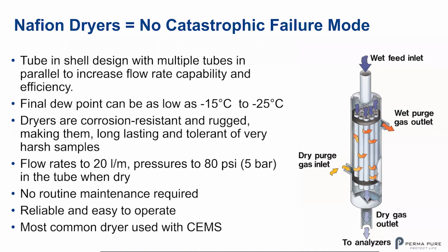So let's take a look at our PD series here. That's the type of dryer that we build into our systems. Those are shown there on the right. It's similar to the other one, but the difference is we have multiple tubes in parallel. The thing I want to talk about with these is that we have no catastrophic failure mode in these dryers, which is very important when you compare that with electromechanical or electronic systems. What happens over time is that they might get fouled with some dirt, but the performance will never drop instantly from one level to another.